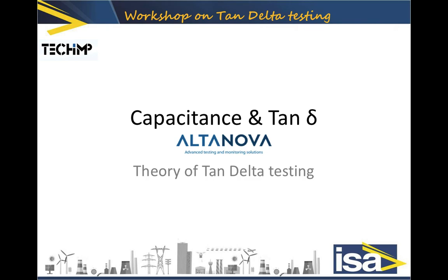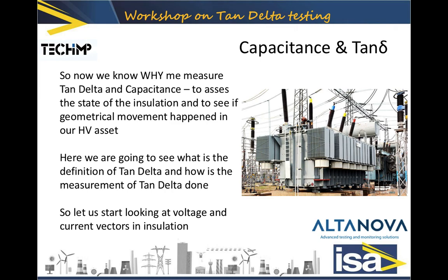In this video we're going to go a little bit more in depth. We're going to see how current and voltage behave in those schemes. We also saw last time that even a small current in phase with high voltage generates heat that weakens insulation and brings about a chain reaction which can result in a fault on a high voltage or medium voltage asset. We measure tan delta and capacitance to assess the state of insulation and to see if geometrical movement happened.